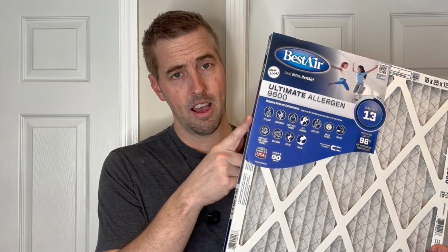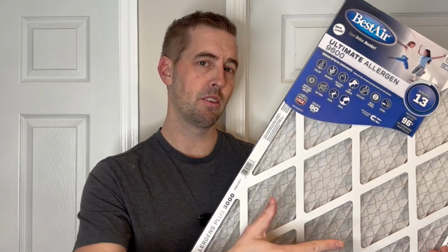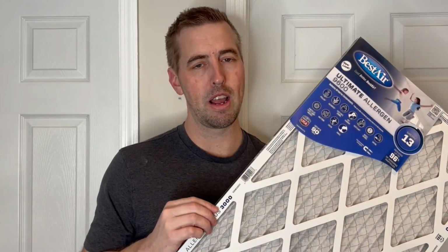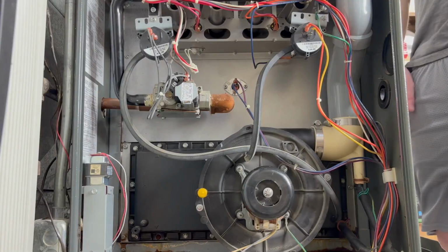And on the contrary, the higher MERV filters, they're going to do a much better job of filtering things through the air, dust, pollen, things like that. So there's trade-offs between the cheaper and the more expensive filters, but in the end, it's all about finding the right filter and seeing how each filter can affect the system performance. And when it comes to filters and MERV ratings, think of this analogy. A really thick milkshake, what's going to be easier to drink it with? A really thin straw or a really wide straw? The wide straw is going to require much less effort. Same goes with filters. A higher MERV rating or a tighter filter is going to require much more effort out of the blower than a lower MERV rating that's going to allow more air to pass through easier. And with that out of the way, let's go ahead and take a closer look at each of the filters we're going to be testing today.